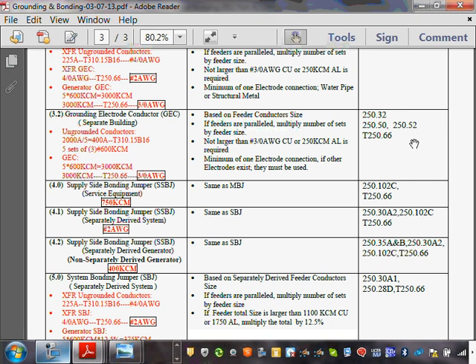And I added a very important thing here: non-separately derived system generator. It doesn't matter if it's a separately derived system or a non-separately derived system. If your circuit breaker is inside the switchgear, that wire is called a supply side bonding jumper and its size is 400 kcmil. And all this is right in these articles. The only difference is if you put your circuit breaker right at the generator, then it becomes, what do we call it? An equipment grounding conductor.